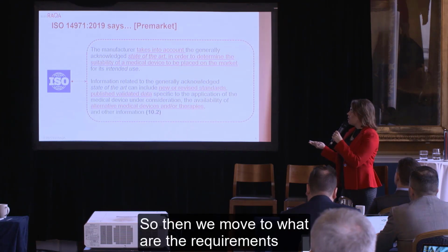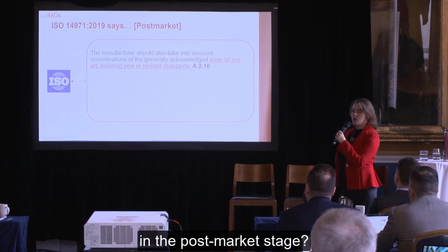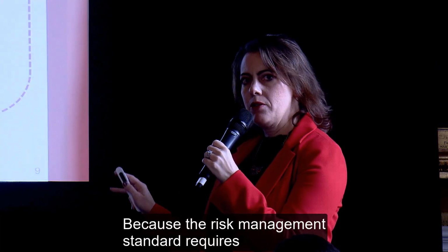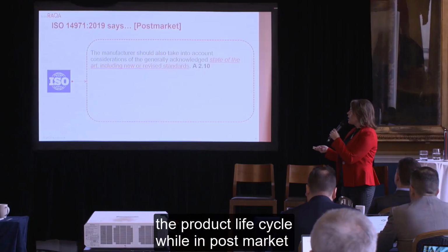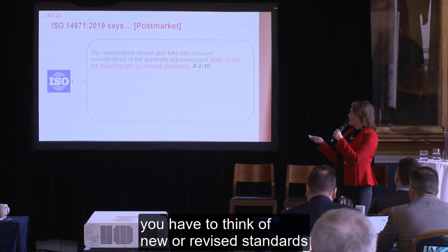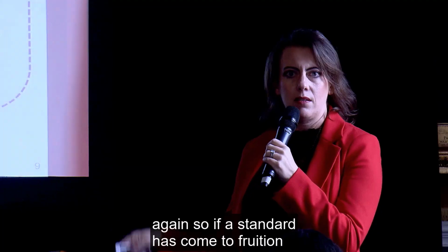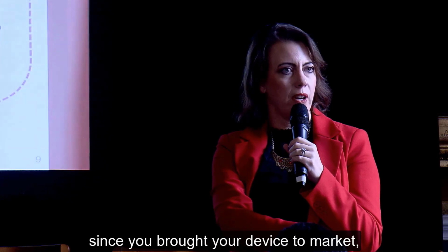So then we move to what are the requirements in the post-market stage? Because the risk management standard requires you to think about state of the art throughout the product life cycle. Well, in post-market, you have to think of new or revised standards again. If a standard has come to fruition since you brought your device to market, now you have to comply with this new standard.